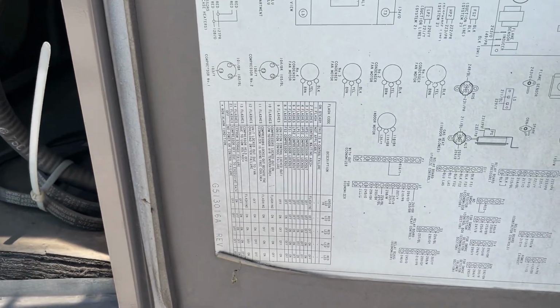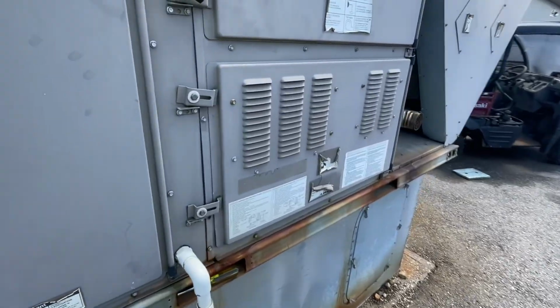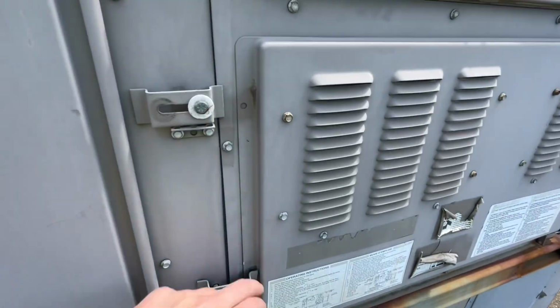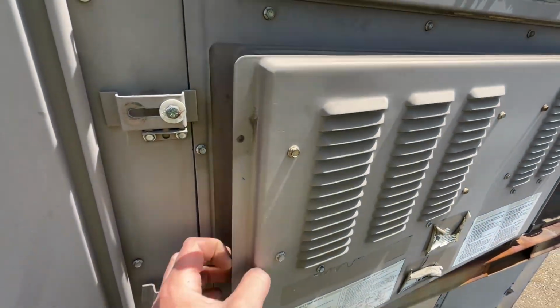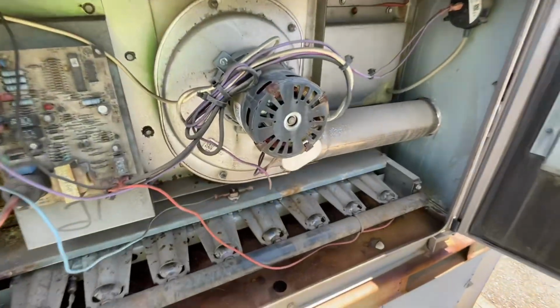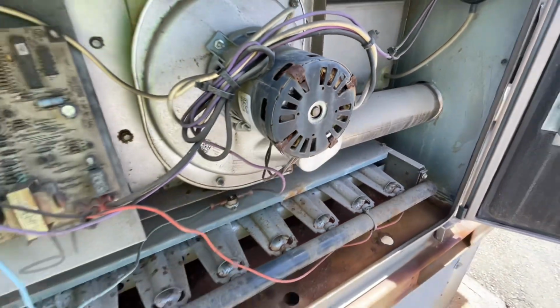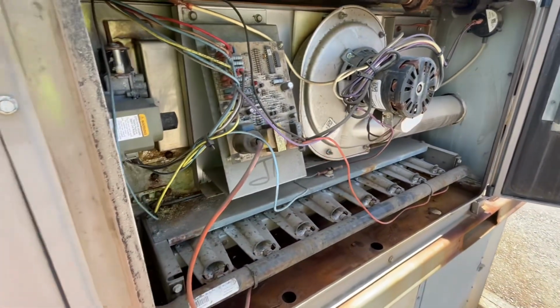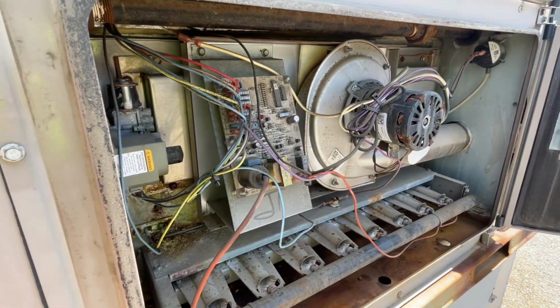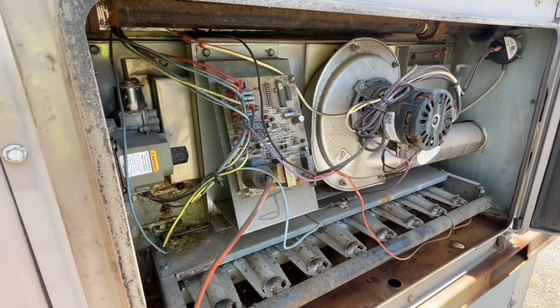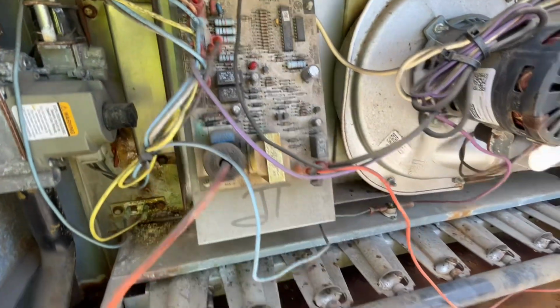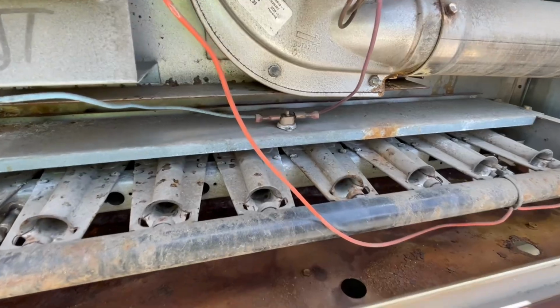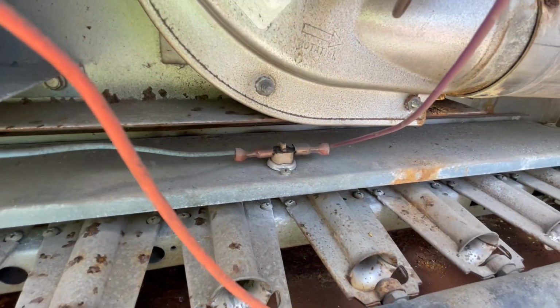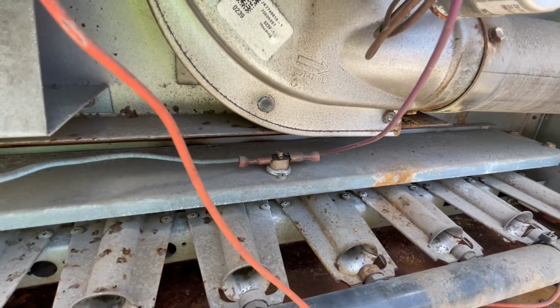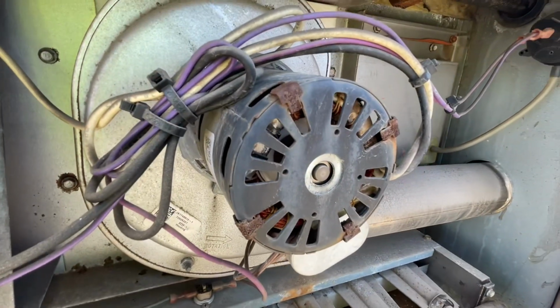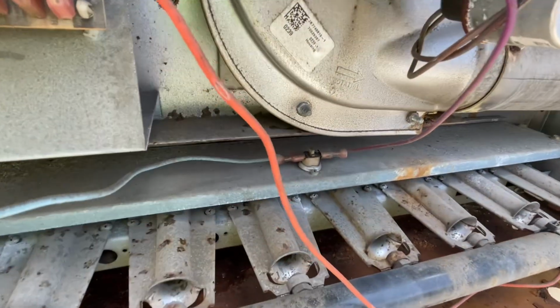Let's take a deeper dive into this. Here's our burner door. Our inducer motor is behind here. It's running, and it shouldn't be because it's been hot as hell. I don't see any reason why the heat should be on or even trying to run right now. So I immediately see a manual reset rollout switch. So when that switch is open or tripped, this motor will run 24/7. So we're gonna try this first.